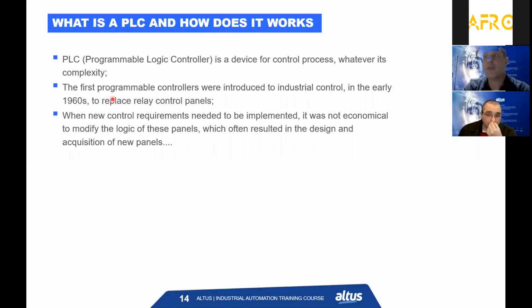The first programmable controllers were introduced to industrial control in the early 60s to replace the relay control panel. When new control requirements needed to be implemented, it was not economical to modify the logic of these panels, which often resulted in the redesign and acquisition of new panels. So that's why, with the PLC, you can see that we save money, because we can introduce new features and new functionalities without having to rebuild and redesign the application.